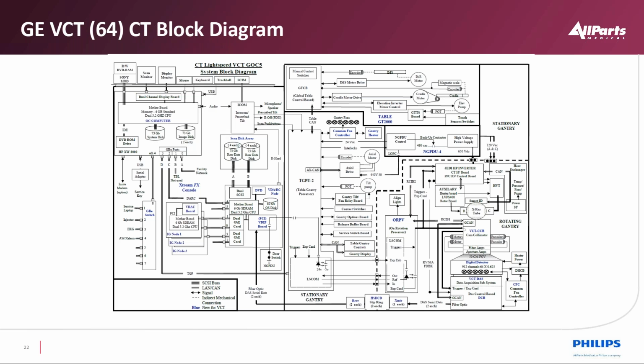Then we get into the real details. This represents a GE VCT 64 slice. As you can tell, even with the controllers and the subsystems, there are a lot of things going on at a given time. We have a lot of hardware moving at the same point in time as we're generating high voltage for X-ray, generating the X-ray beam, controlling the collimator, triggering the detector to receive that data, transmitting that data to the recon subsystem, and then ultimately reconstructing that data and having a completed image displayed on screen. So it's a very quick process, with a lot of things to relay as far as how we troubleshoot a machine and make sure everything's working.